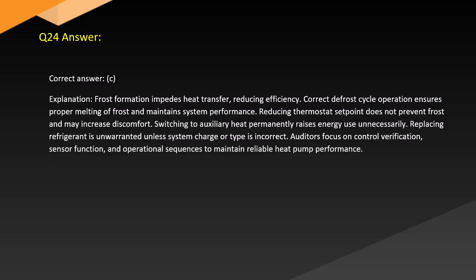Answer. Correct answer. C. Explanation. Frost formation impedes heat transfer, reducing efficiency. Correct defrost cycle operation ensures proper melting of frost and maintains system performance. Reducing thermostat set point does not prevent frost and may increase discomfort. Switching to auxiliary heat permanently raises energy use unnecessarily. Replacing refrigerant is unwarranted unless system charge or type is incorrect. Auditors focus on control verification, sensor function, and operational sequences to maintain reliable heat pump performance.